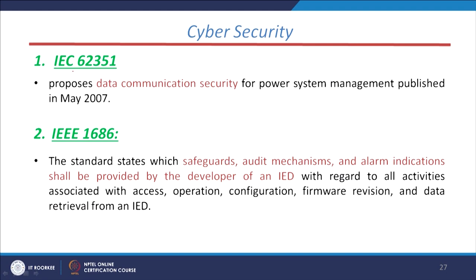The last standard area is cyber security. IEC 62351 is dedicated to data communication security, and IEEE 1686 provides safeguard audit mechanisms, alarm indication, and guidelines for developers of intelligent electronic devices (IEDs) with regard to all activities associated with operation, configuration, and data retrieval. Those standards provide information on how to retrieve data, record data, and determine communication rates for IEDs in the smart grid system.